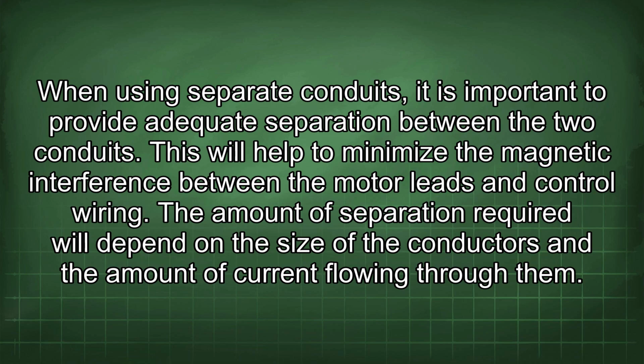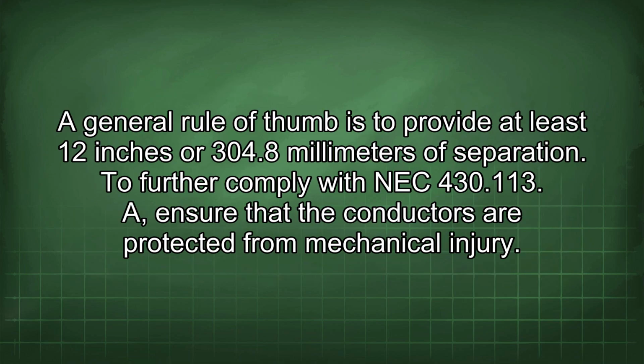When using separate conduits, it is important to provide adequate separation between the two conduits. This will help to minimize the magnetic interference between the motor leads and control wiring. The amount of separation required will depend on the size of the conductors and the amount of current flowing through them. A general rule of thumb is to provide at least 12 inches or 304.8 millimeters of separation.